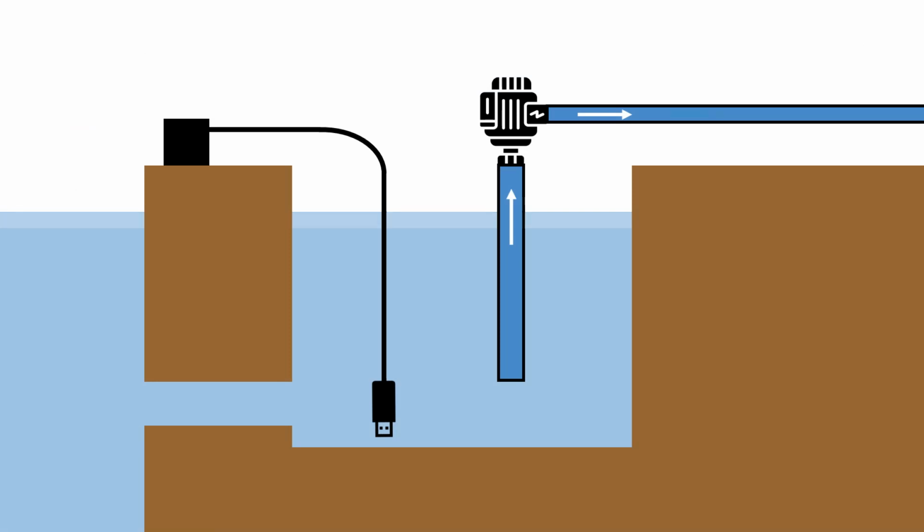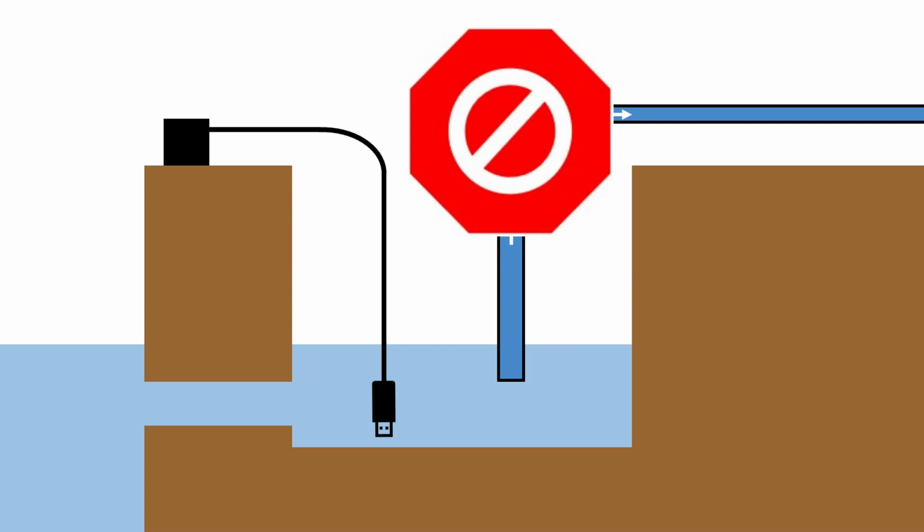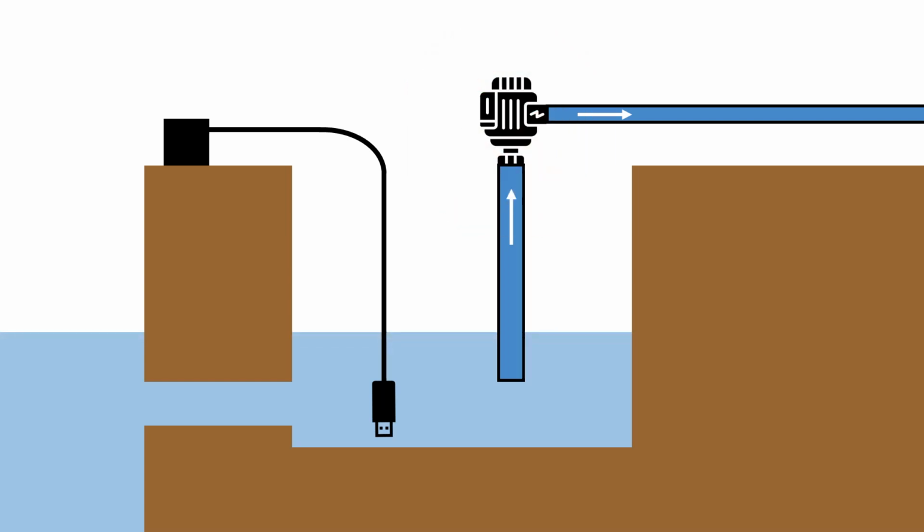Here's what happens with these values. When the water level in the wet well drains down to that lowest level, and the sensor reads 0.86 PSI or less, this water source can't be used and it's taken offline. After 4 hours, it will check to see if the water level has come up again. If the level has increased and there's more than 0.86 PSI at the sensor, the wet well water source, the one that's connected to our pump, will start watering again. If the well is still dry or below that 2-foot level, it'll wait another 4 hours before checking again. Water source empty conditions are a great way to ensure that a wet well or other water source is not used when the water level is too low.